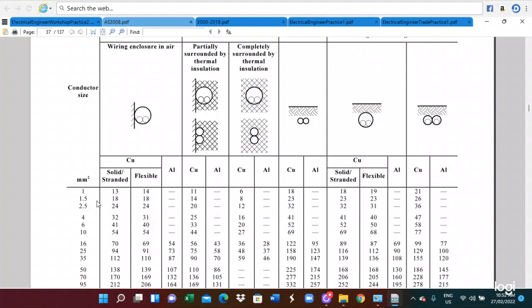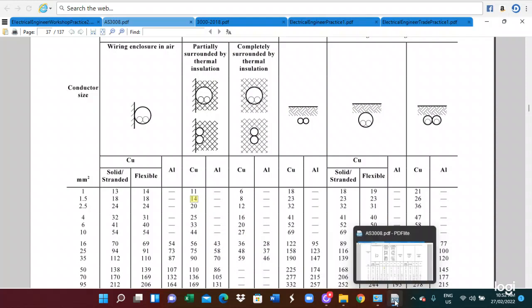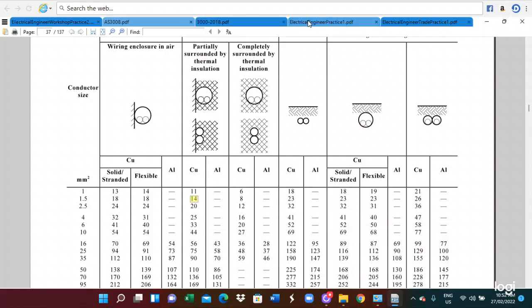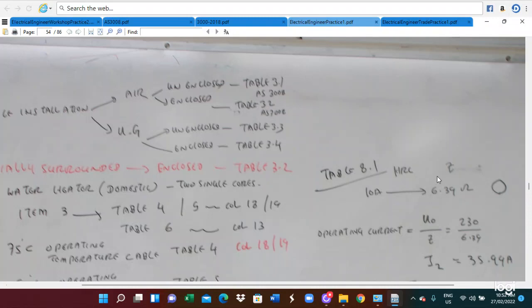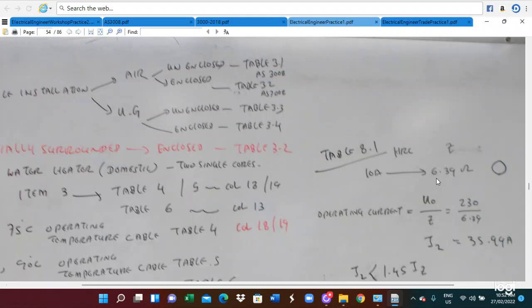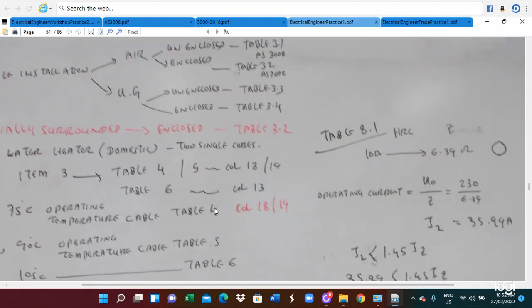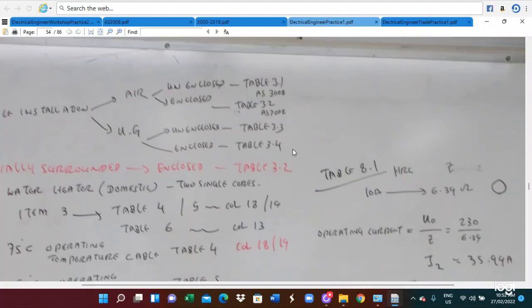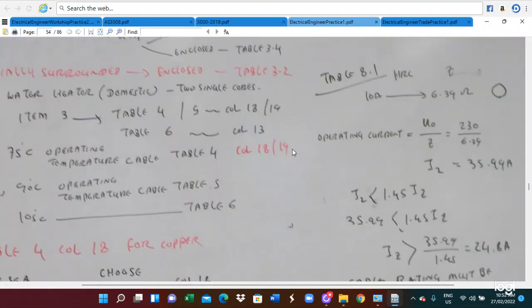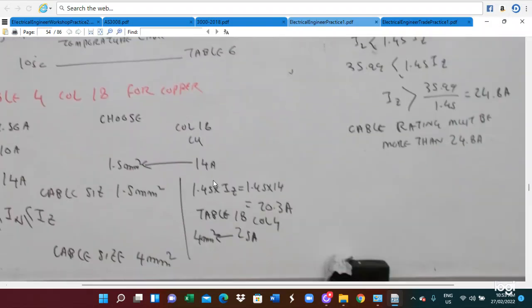The minimum cable size is at least 1.5mm². For 1.5mm² copper cable, the current-carrying capacity IZ is 14A. So the fuse rating IN = 10A and the cable rating IZ = 14A. We check the first condition: IB (9.56A) ≤ IN (10A) ≤ IZ (14A) — this is satisfied.